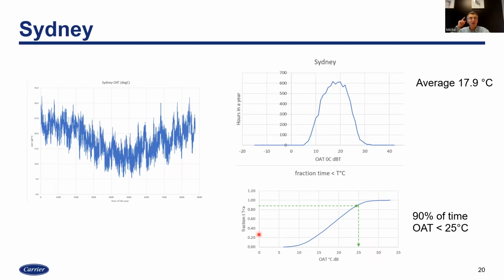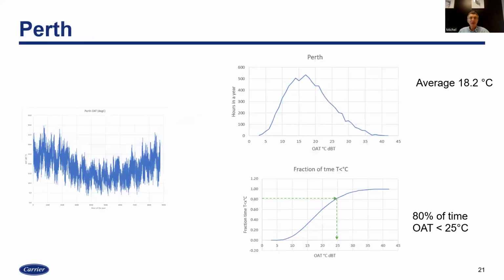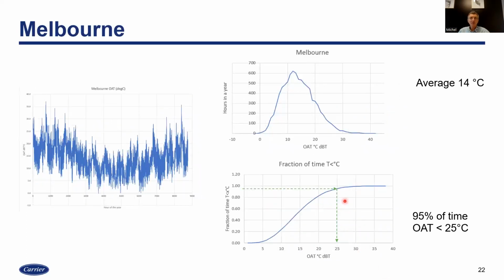What I'm saying is, it gives you an idea of what percentage of time I can access, or will operate in, free cooling. So for instance, if we start to activate free cooling at 25 degrees C, you will see that in Sydney, almost 90% of the time you will be activating free cooling mode. Okay, so this is very interesting. And I did this for other places. Perth has a different distribution, a different set. But in Perth, if you are looking at 25, only 80% of the time you have a chance to activate free cooling if your water temperature is 30-20. In Melbourne, 95% of the time.